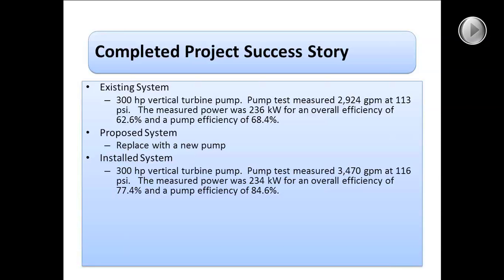And so really the energy savings here, you can run with the higher flow rate, same pressure pretty much. You can run more of the system at one time at the same demand in kilowatts, but you don't have to run as many hours now because you can run more lines at one time and get over the system quicker. There's a picture of the project. The pump in the middle is the new pump.